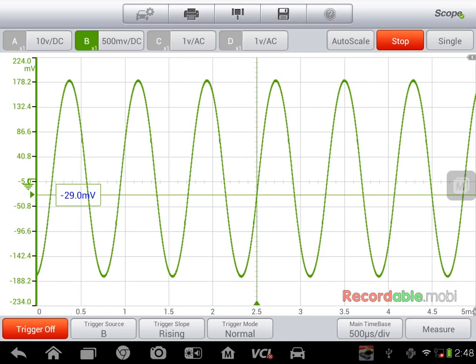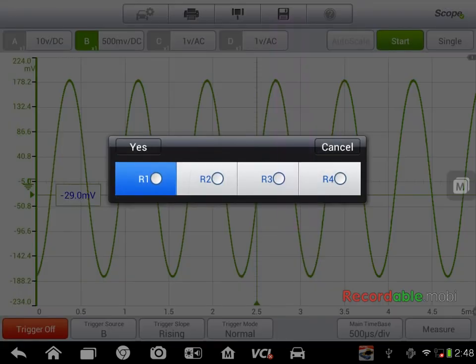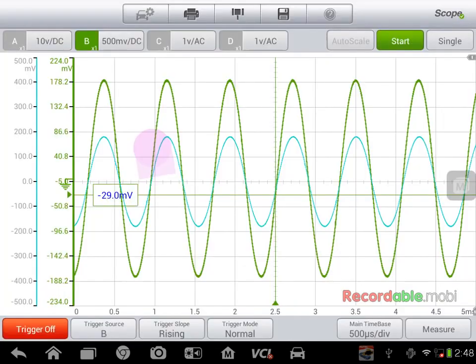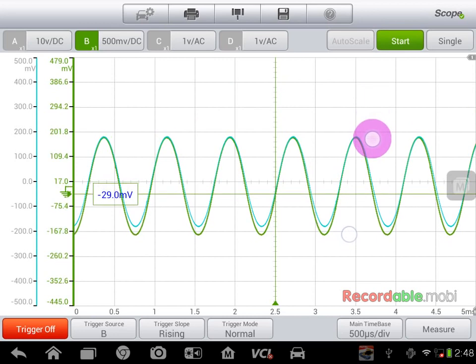So if I'm working on multiple circuits and I have one that I know is good, I can actually revisit that by recalling reference R1, yes. That will put the known good reference on the screen, and then as I have my new signal, I can bring that down to make sure that they match, or to notice any imperfections in that signal.